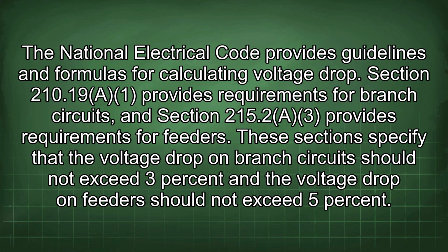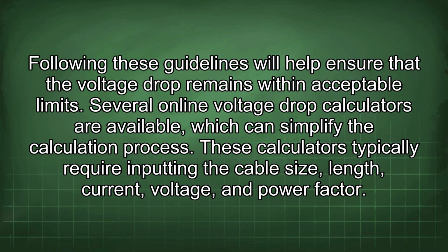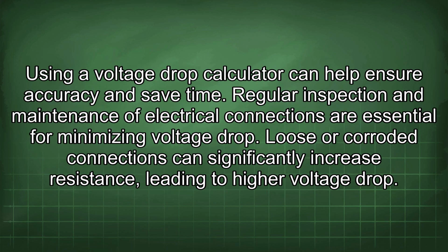The National Electrical Code provides guidelines and formulas for calculating voltage drop. Section 210.19(A)(1) provides requirements for branch circuits, and Section 215.2(A)(3) provides requirements for feeders. These sections specify that the voltage drop on branch circuits should not exceed 3% and the voltage drop on feeders should not exceed 5%. Following these guidelines will help ensure that the voltage drop remains within acceptable limits. Several online voltage drop calculators are available, which can simplify the calculation process. These calculators typically require inputting the cable size, length, current, voltage, and power factor. Using a voltage drop calculator can help ensure accuracy and save time.